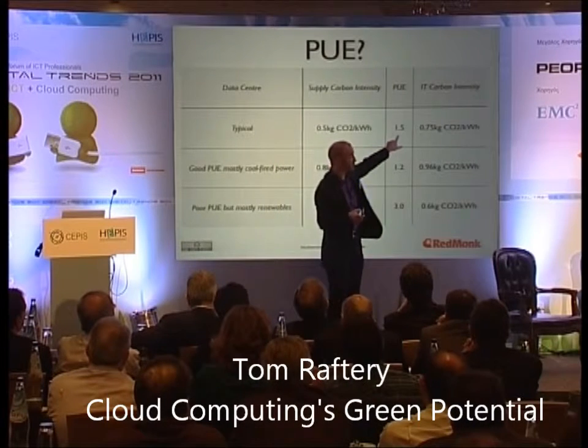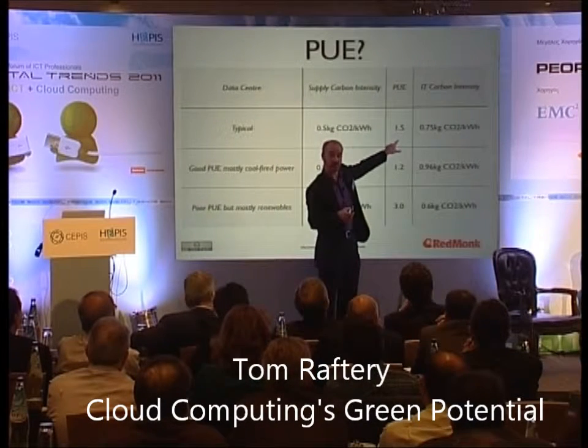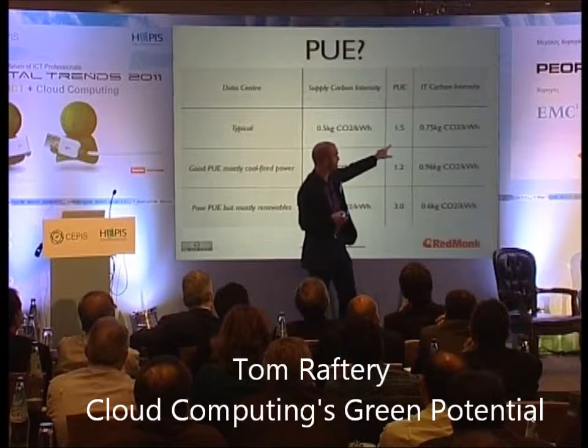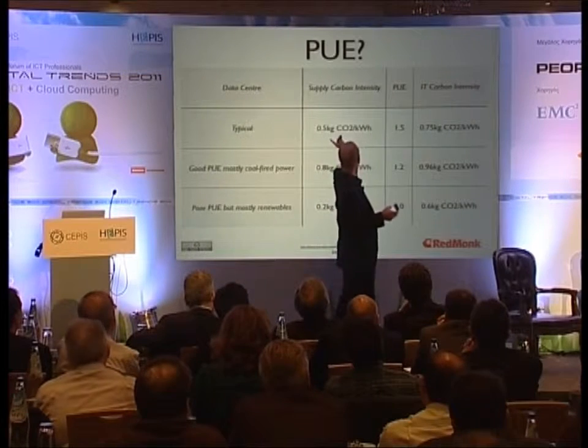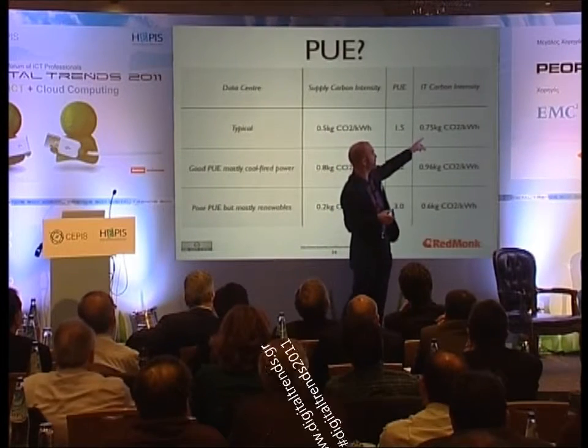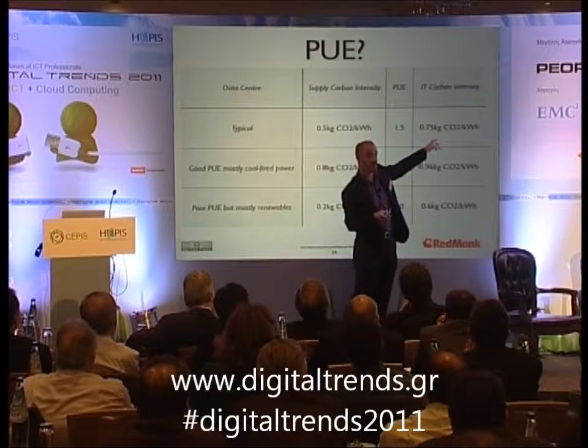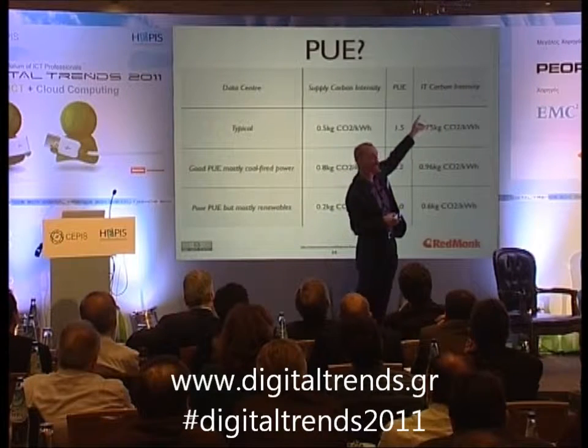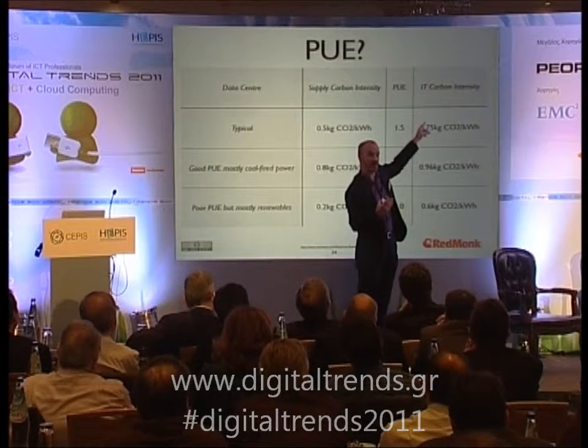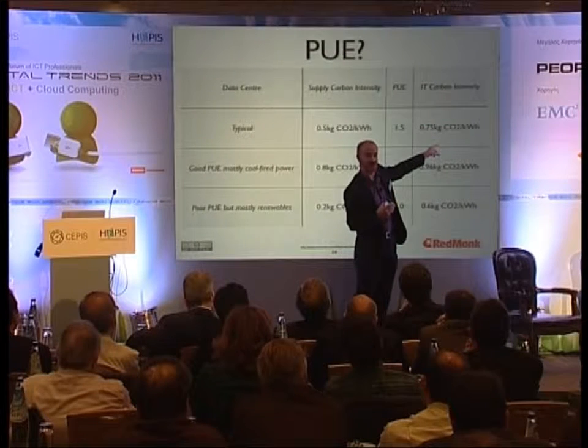If the typical data center has a PUE of 1.5, which is quite good, then we get 1.5 times 0.5, giving us 0.75 kilograms CO2 per kilowatt hour as the IT carbon intensity — how much the IT equipment is producing in terms of CO2.